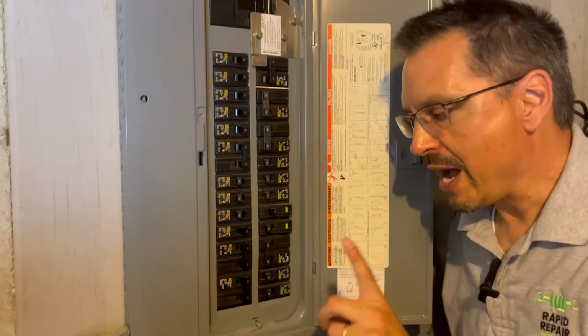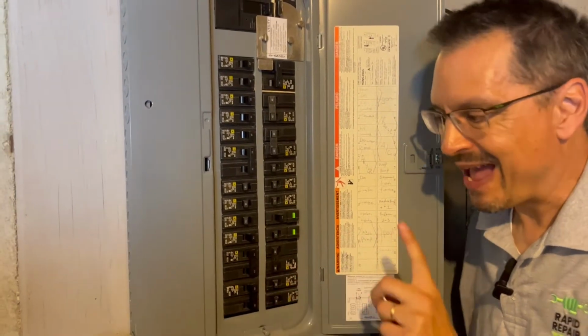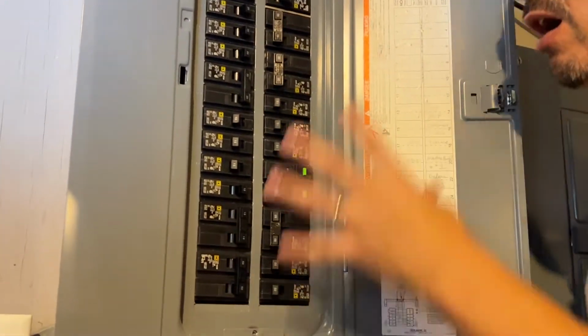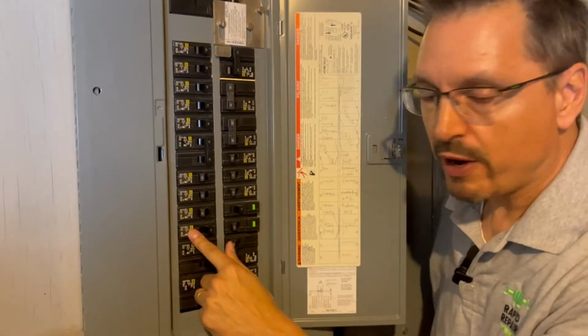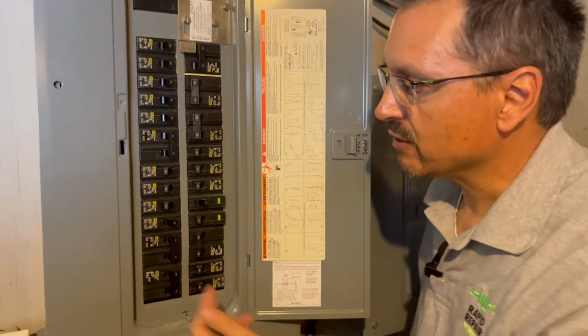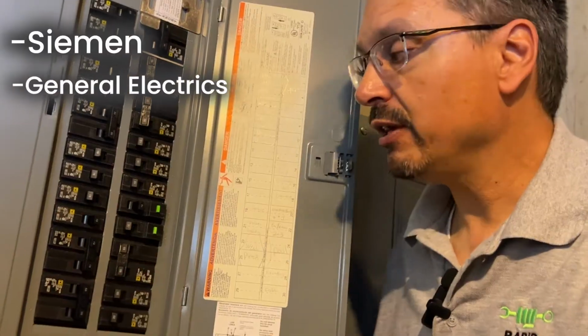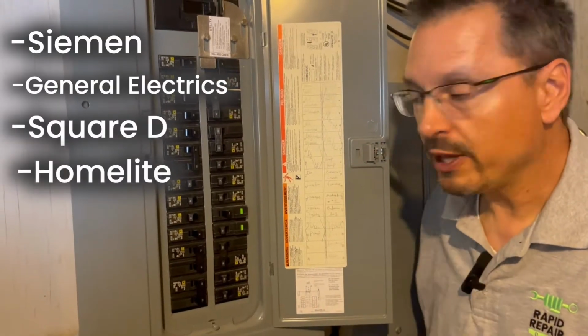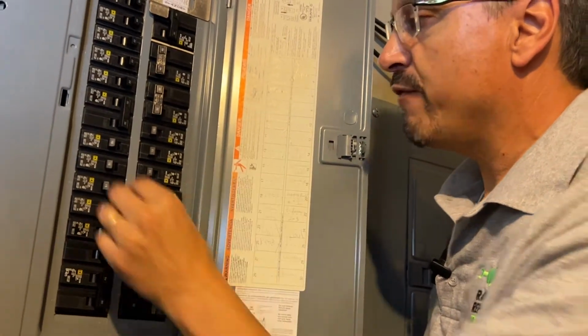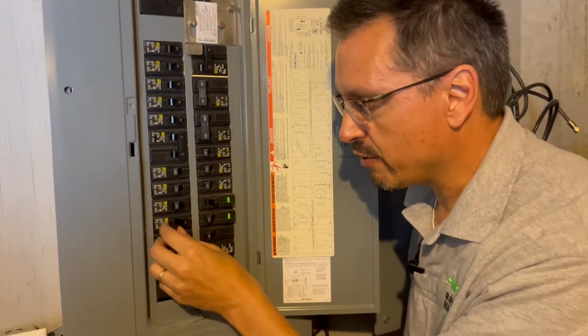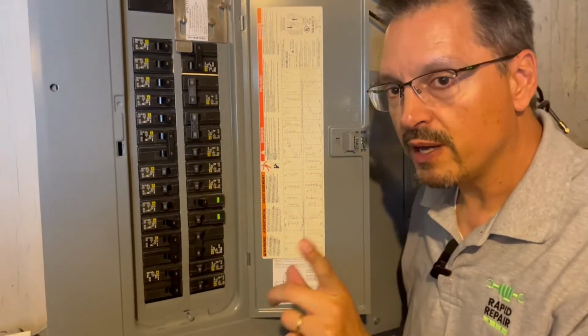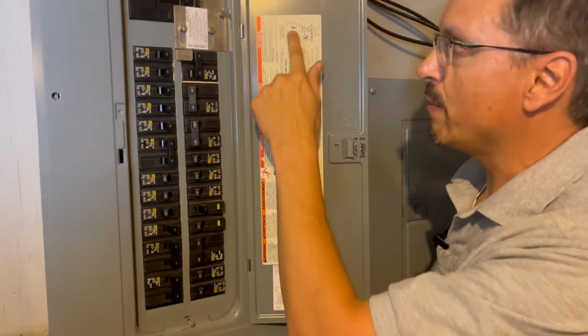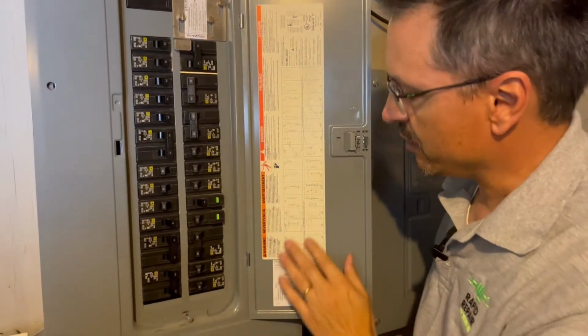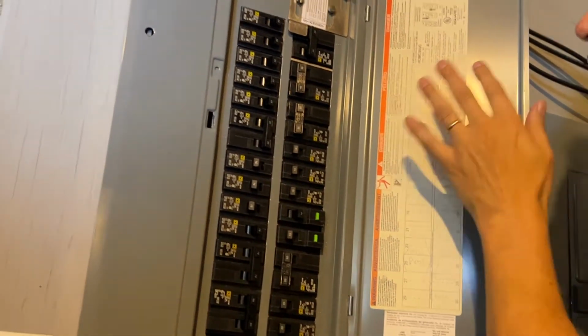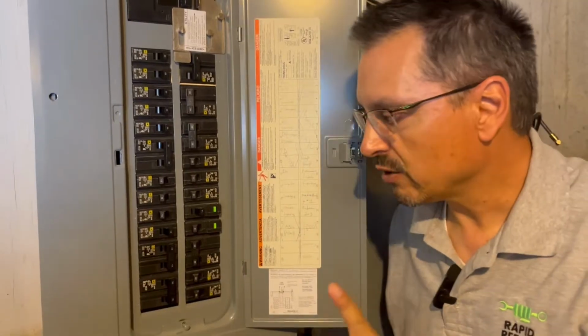When you go to buy your replacement circuit breaker, you have to buy the same brand of the panel. So this is Square D. You may have different brands, say Siemens, General Electric, Square D, Homeline. There's different brands out there. Now, if you have mixed match circuit breakers and you're replacing a damaged one, you must buy the one that's going to match the panel or be compatible with the panel. So look for your panel manufacturer, read the instructions, and you will get the right circuit breaker.